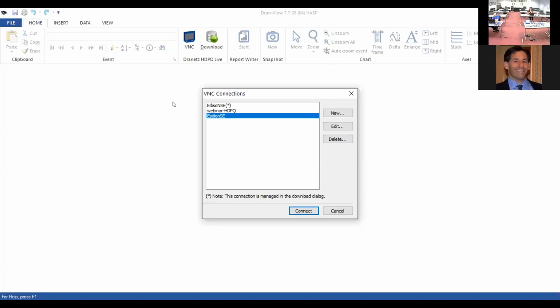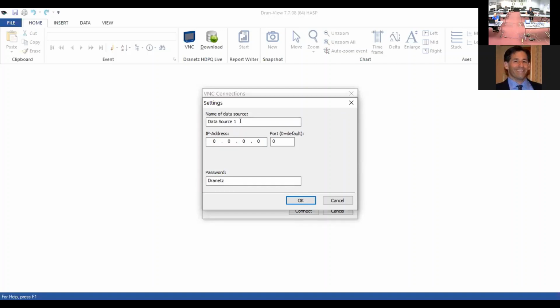So if I'm setting up a remote session to an instrument, I would simply go to New, and then I will give the session a name. You can see here it uses a default name, and then I would enter the IP address, and I'll show you later an IP address setup. So I would enter the IP address that's been assigned to the instrument.